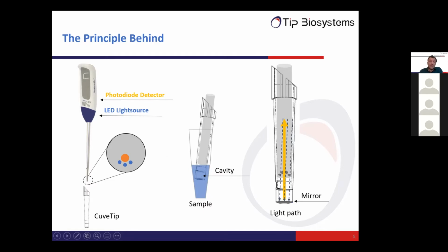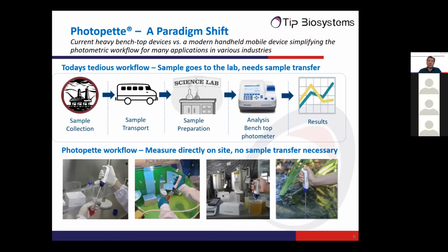So this means that by dipping the tip into the liquid for at least 3 millimeters, the tip is filled with your sample. And in this internal volume, the light is reflected back and forth, and the absorbance is measured. So with these features, the Photopette is inserted into the sample, but the sample does not come to the Photopette, so there's a very different workflow.